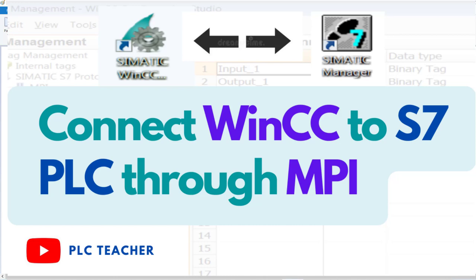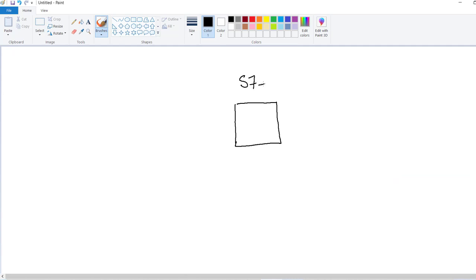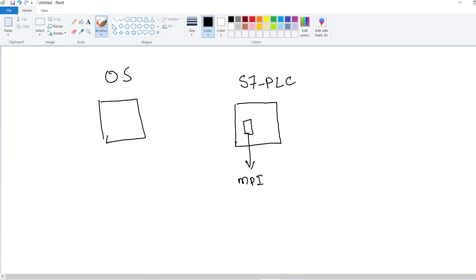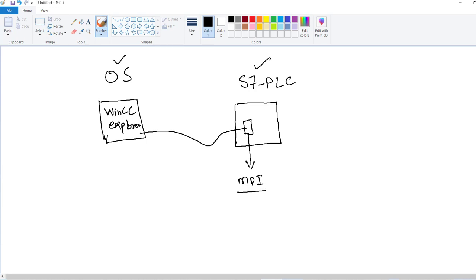If you have an S7 300 PLC and an operator station with WinCC and you want to communicate data between them through an MPI cable, the S7 PLC has an MPI port. On the other hand, you have an operator station — a PC with WinCC software installed. Connect the MPI cable between the S7 PLC and the operator station: the serial end goes to the PLC side, and the USB connector goes to the USB port of the operator station. This is the physical connection of an S7 PLC with a WinCC operator station.